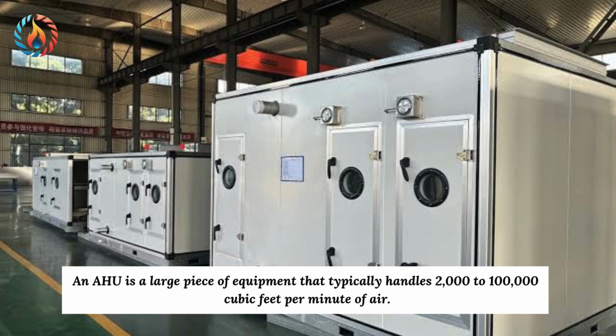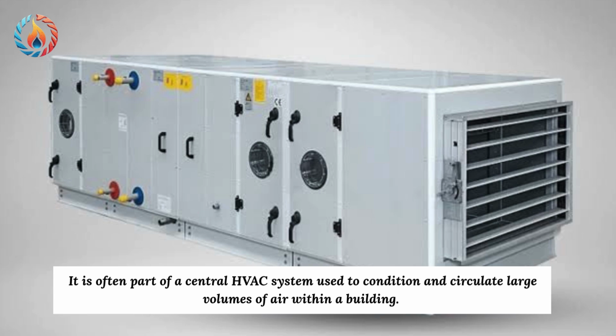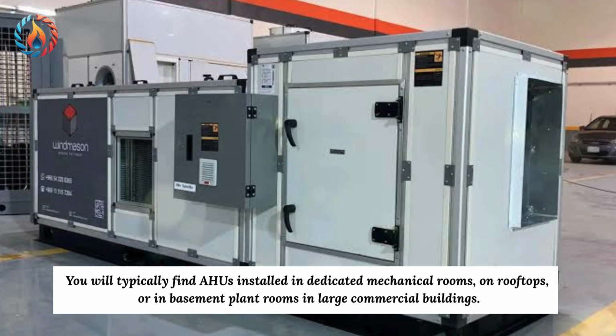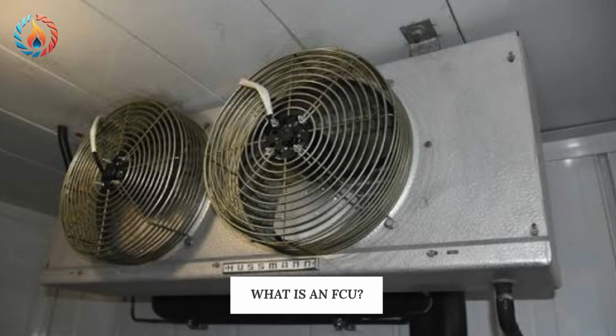An AHU is a large piece of equipment that typically handles 2,000 to 100,000 cubic feet per minute of air. It is often part of a central HVAC system used to condition and circulate large volumes of air within a building. You will typically find AHUs installed in dedicated mechanical rooms, on rooftops, or in basement plant rooms in large commercial buildings. What is an FCU?